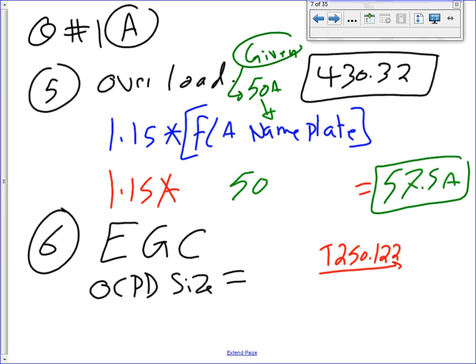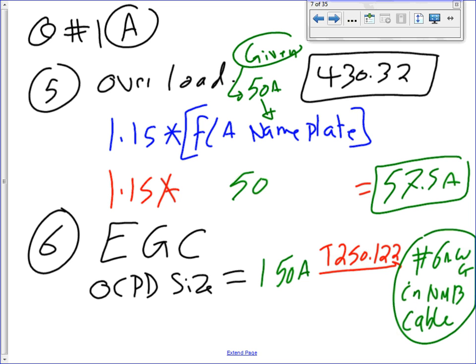The last thing, guys, is the equipment grounding conductor. The equipment grounding conductor is very easy. We size it based on the 150 amp. If you go to 250.122, it will get you a healthy number: 6 AWG in NM-B cable. Remember, we're using a cable, so that's not a conduit. So it's going to be part of that cable. I don't know if they make a number 6 equipment ground conductor with it, but that's the minimum size that you want. Okay.